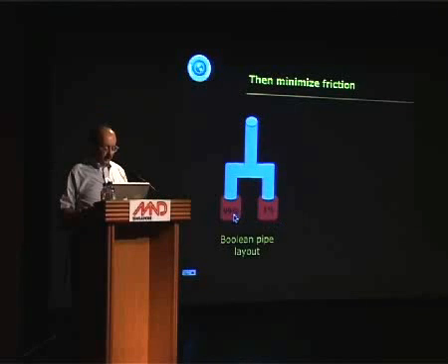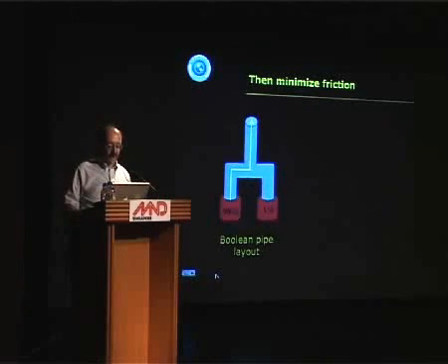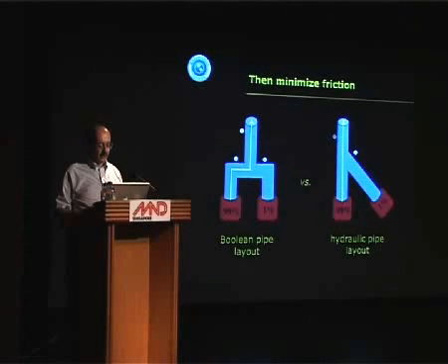Very often you see a pair of pumps, either helper pumps or an in-place spare for a critical pump. They're laid out like this because they're drawn like this, then they're built like this. So all the time the flow goes through 2 right angle bends, extra friction, then it goes through 2 valves. Why don't we do it with no bends and no valves or 1 valve? Well, we're just not used to it.